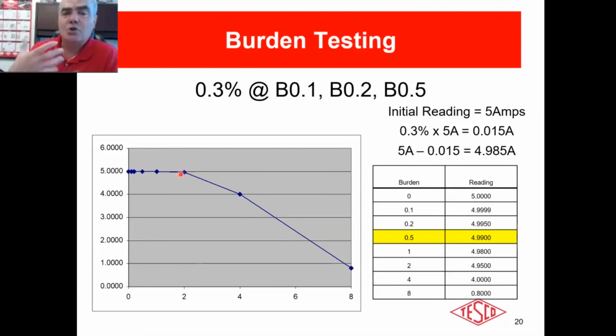I've got too much burden on the secondary, too much burden in that service. No matter how good my meter, no matter how good my current transformer, it's just not going to give me the accuracy I expect. And you can see how badly it starts to fall off here once you get past this knee. It really starts to fall off quite badly.